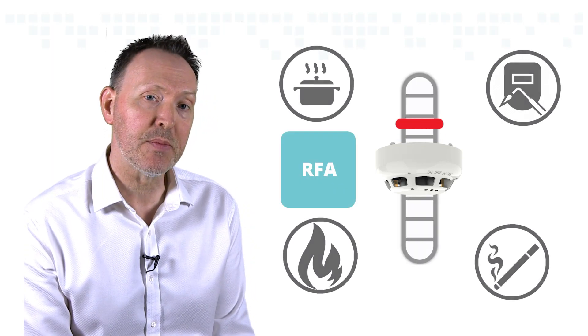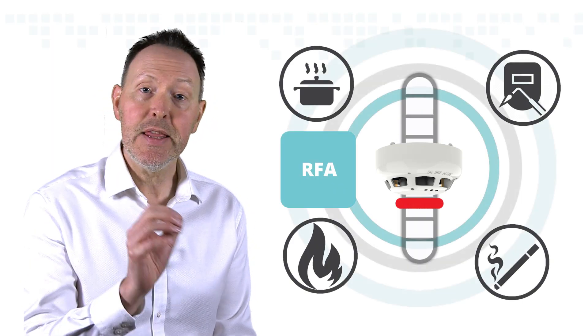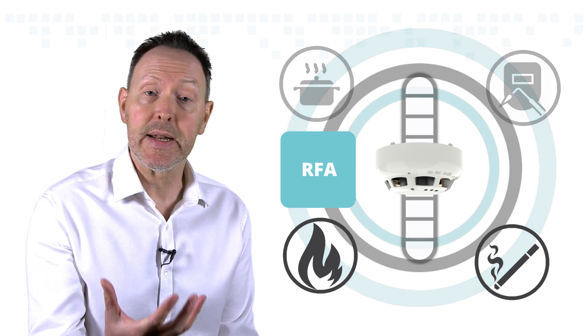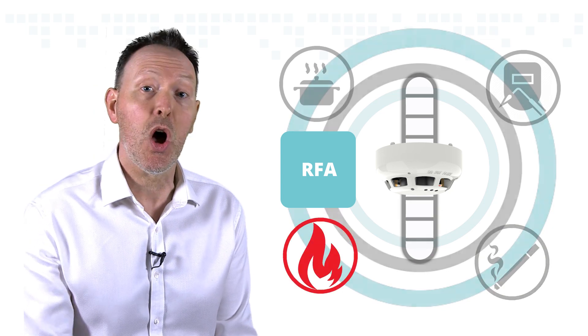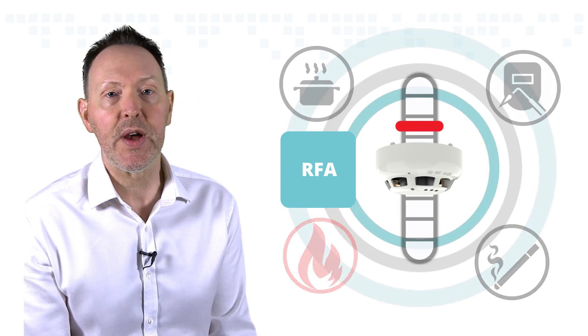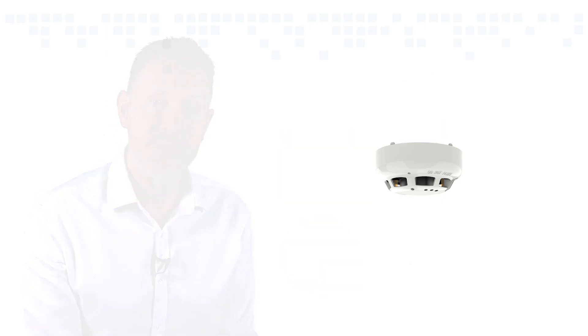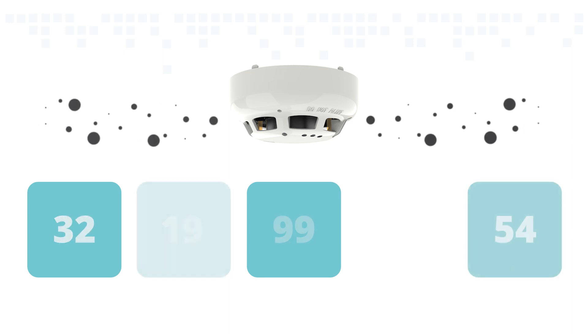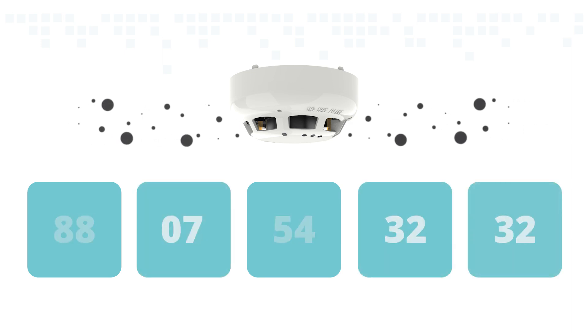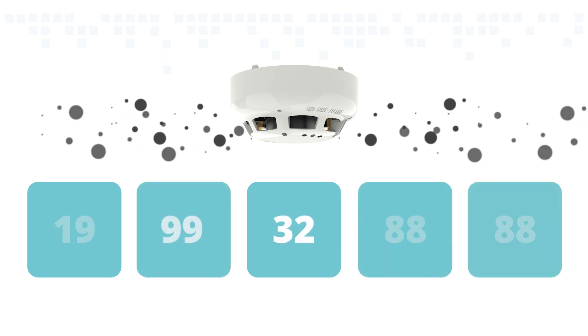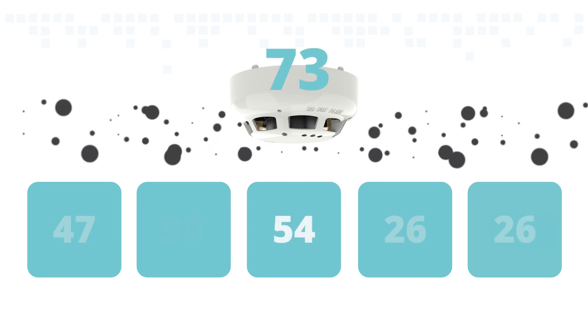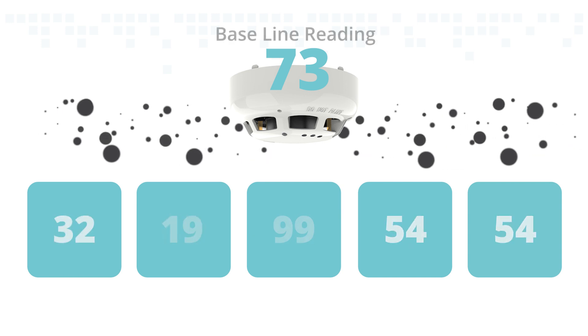The ACD has also been developed with the reduction of false alarms in mind with some clever software features. In the modes featuring the reduced false alarm function, the sensor will automatically adjust the sensitivity of the optical sensing element over time, learning from its surrounding environment in the moment of installation. It does this through a highly sophisticated algorithm which continually monitors the analogue value reading from a series of multiple samples of the environment and calculates an average value.